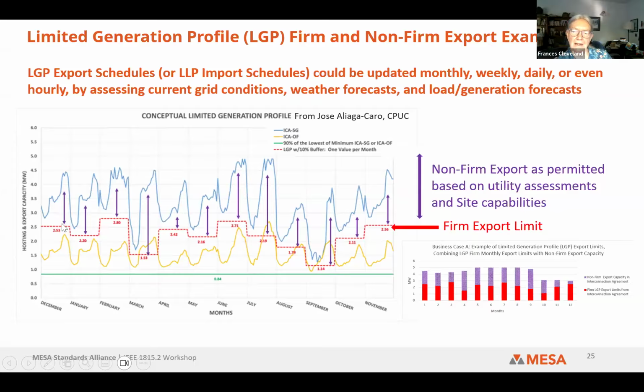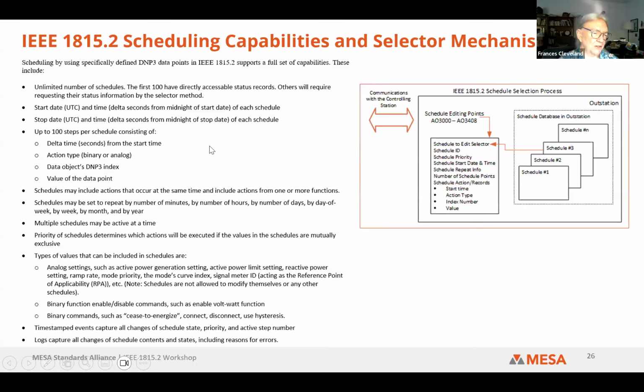So the purple arrow says, okay, the limits really can increase at this point. It doesn't have to be limited to the red line. And up here, again, anytime you have the blue line going above the red line, you actually could increase your export capability, but you need a schedule to do that. And so we have developed, I won't go into the gory details of this because that can be a little on the detail side, but one of the other sessions that we have can go into it in more detail. We have developed a complete scheduling capability.